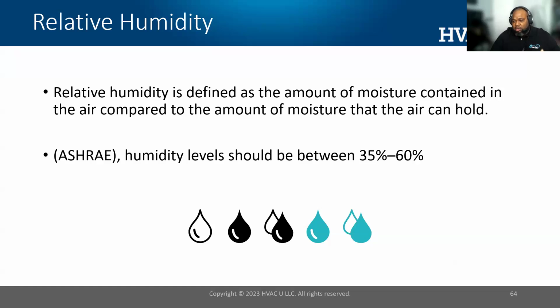So when you're watching the news and the weatherman says 50% relative humidity, you have a reference point of roughly how it's going to feel that day. ASHRAE, the American Society of Heating, Refrigeration, and Air Conditioning Engineers, basically says humidity level should be kept between 35 and 60%, and that also has to do with the type of climate you're in and what mode of HVAC you're operating in.